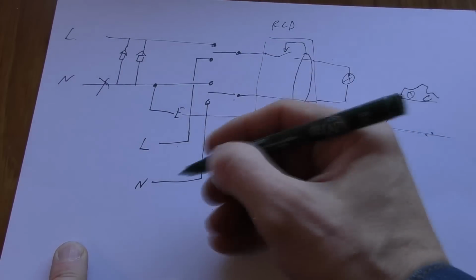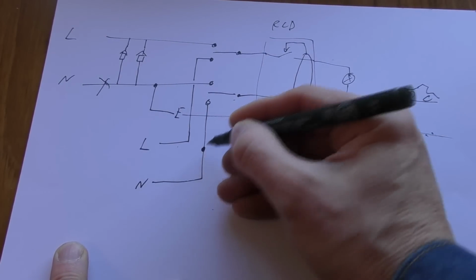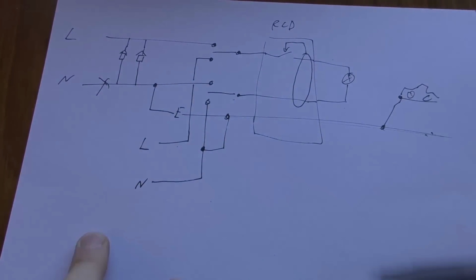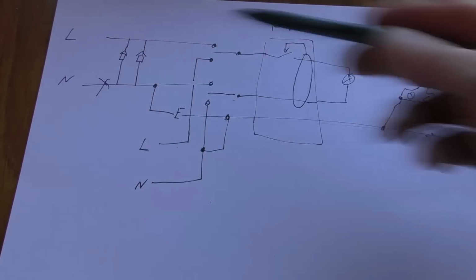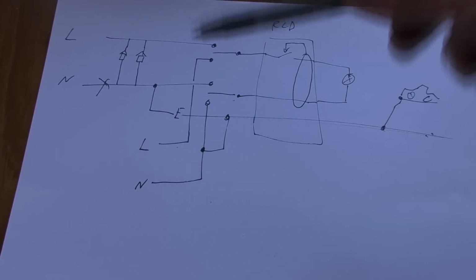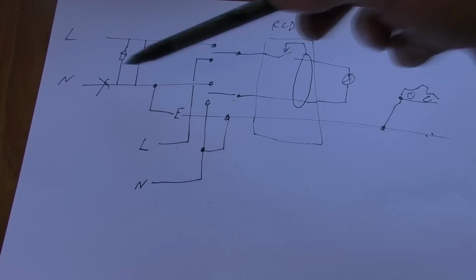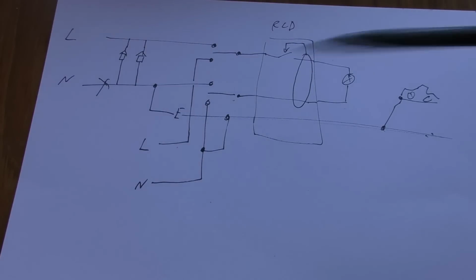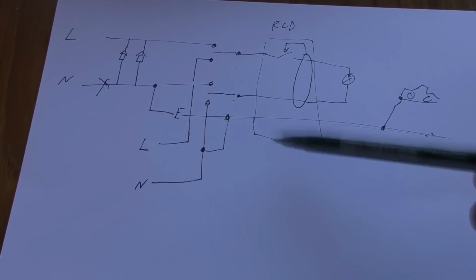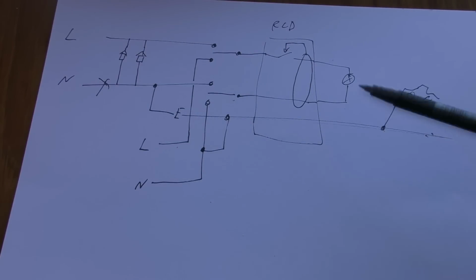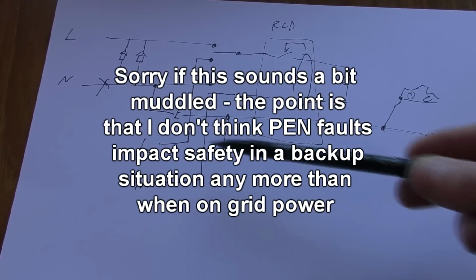What you could perhaps do is link the neutral of your backup port to earth there, to effectively simulate the effect of neutral to earth bonding on the incoming supply. Then your RCDs would work. I don't think there's any particular downside of doing that. So you would get the RCD protection because this source was no longer floating.